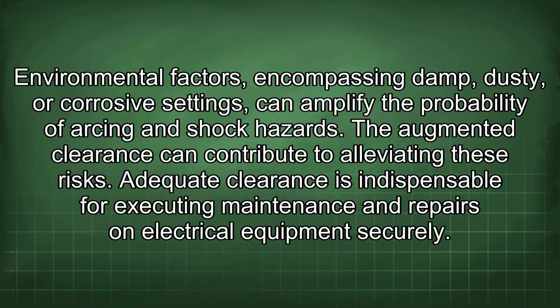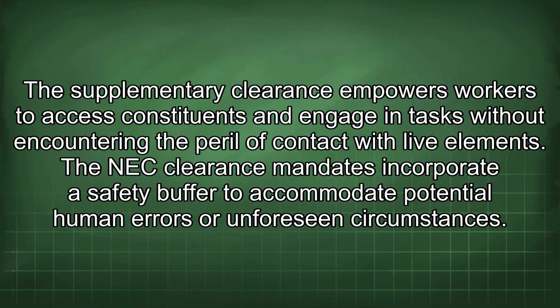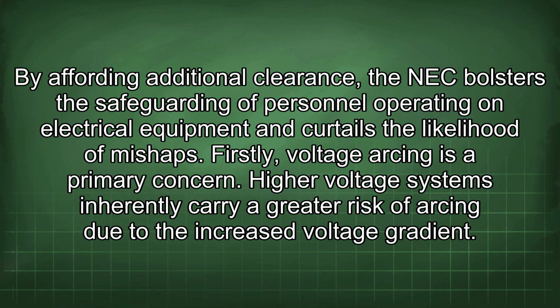Adequate clearance is indispensable for executing maintenance and repairs on electrical equipment securely. The supplementary clearance empowers workers to access constituents and engage in tasks without encountering the peril of contact with live elements. The NEC clearance mandates incorporate a safety buffer to accommodate potential human errors or unforeseen circumstances. By affording additional clearance, the NEC bolsters the safeguarding of personnel operating on electrical equipment and curtails the likelihood of mishaps.